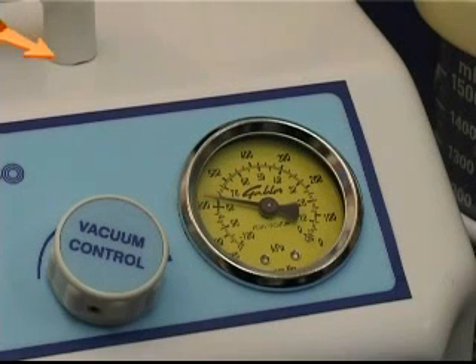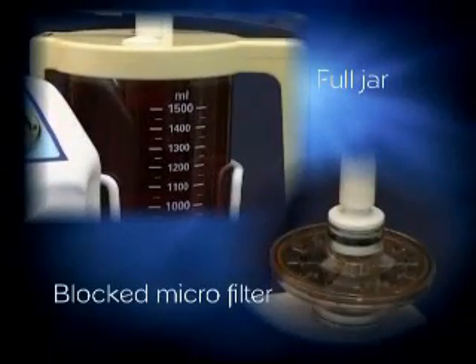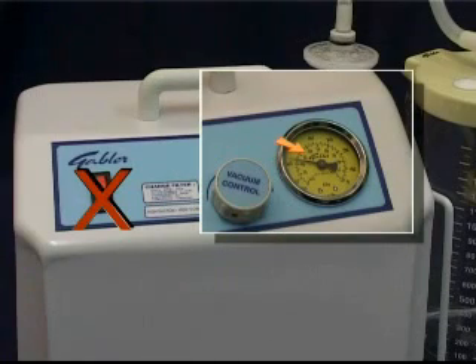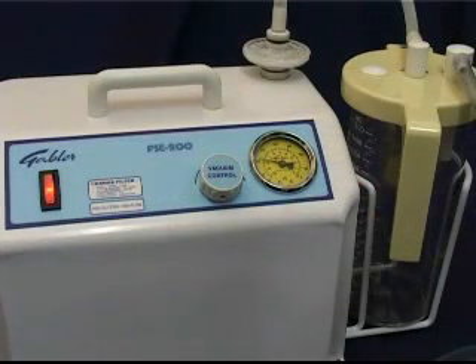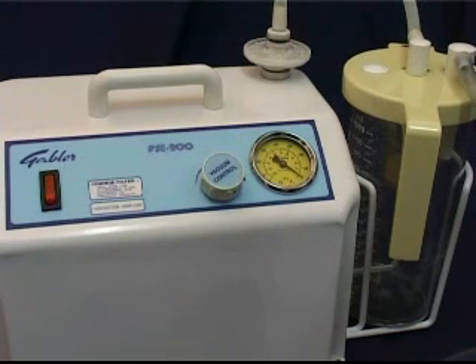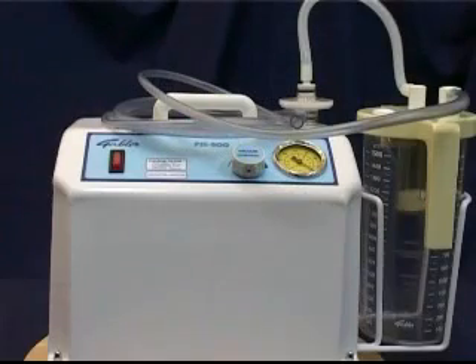It can happen that the pressure gauge shows a reading even though the pump is not running. This can be the result of a full collection jar or a blocked microfilter. Take care never to start the suction pump up against a vacuum. Should the operator accidentally start the unit up against a vacuum, the fuse will blow, protecting the motor from further damage. Should this happen, make sure that the problem is reported so that a technician can be contacted. Do not attempt to replace the fuse yourself.